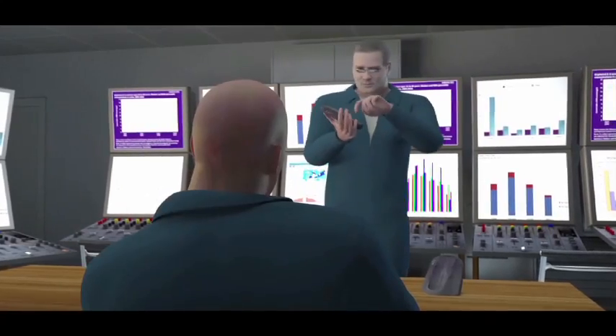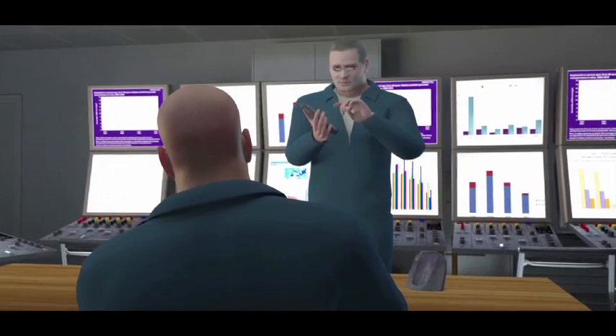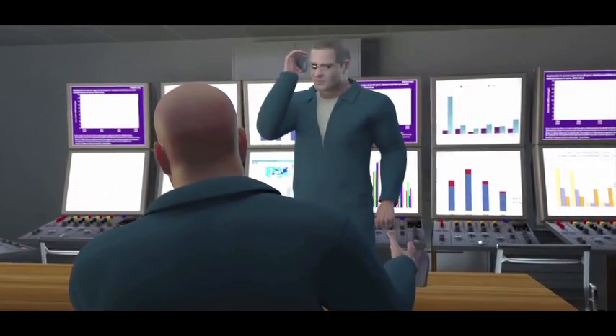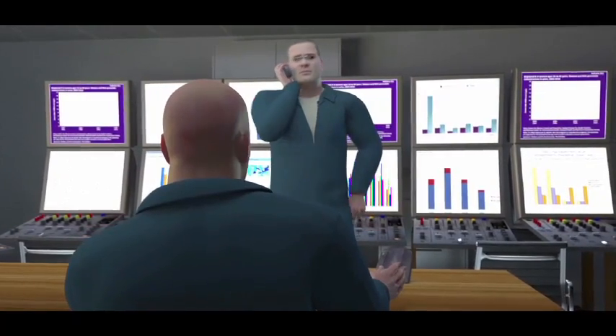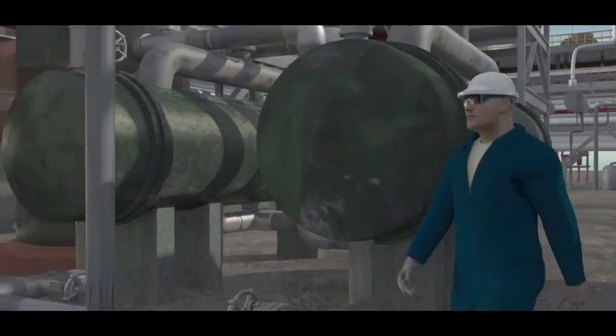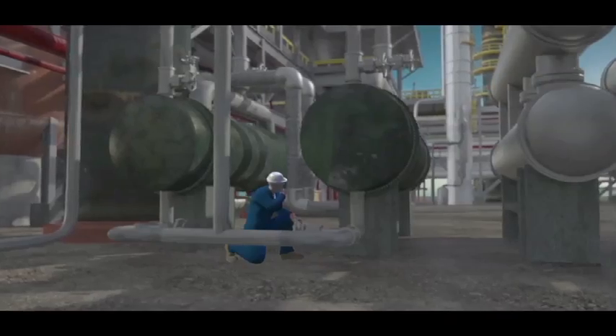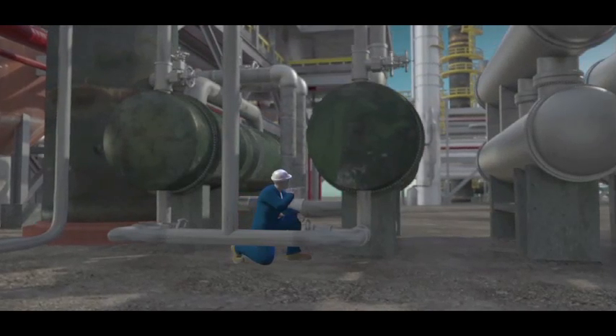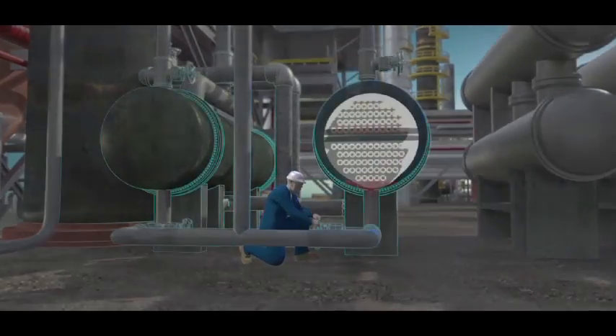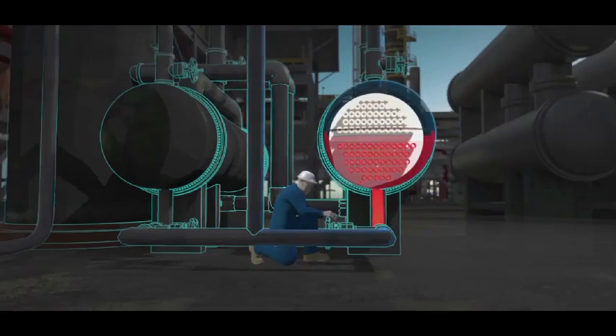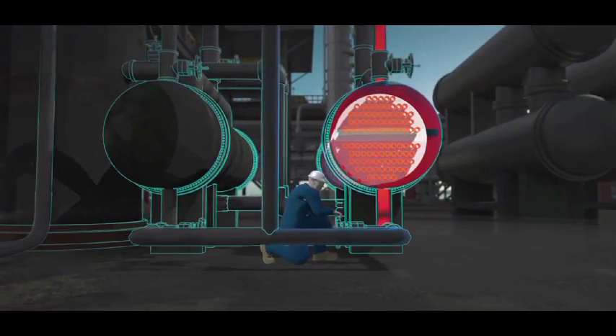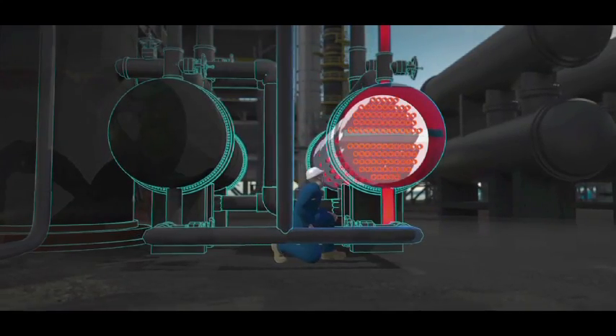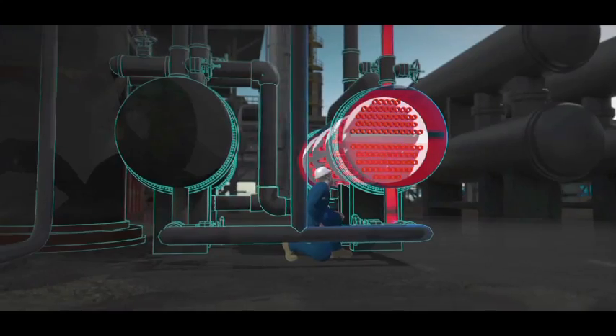The operations supervisor informed several personnel that fouling within the operating reboiler could be the problem, and they might need to switch the reboilers. He attempted to meet with his manager so they could get the necessary maintenance and operations personnel involved who would perform the work. But his manager was not available. The operations supervisor returned to the field. The CSB determined that at 8:33 a.m., the operations supervisor likely opened the water valves on the standby reboiler. Hot water began flowing inside. The valves blocking the reboiler from its protective pressure relief valve remained closed.